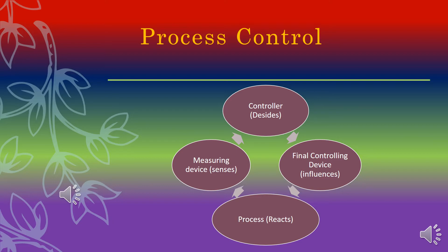Another common term in the industry is the transducer. A transducer is a device that converts one signal into another type of signal, or you can say it's a device that converts one form of energy into another. An example of a transducer is the current to pneumatic converter, which takes the 4 to 20 milliamp signal and converts it into a 3 to 15 psi pneumatic signal. This I to P converter is used in the control valve positioner.